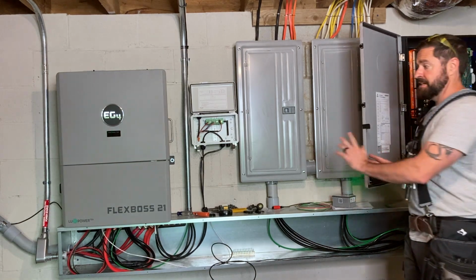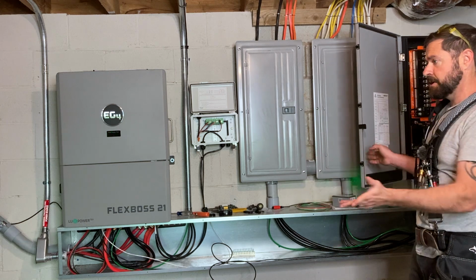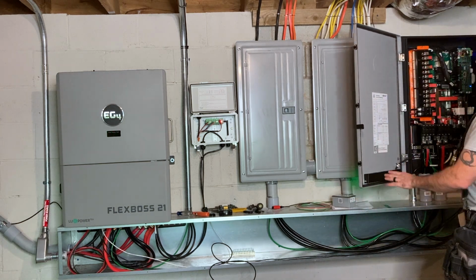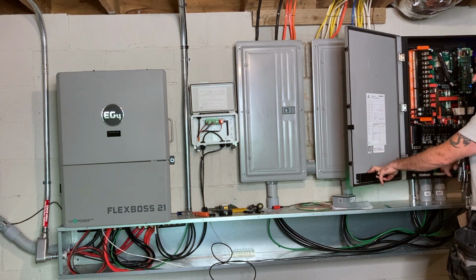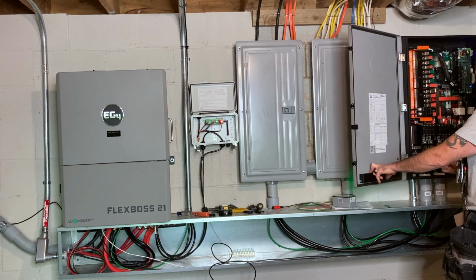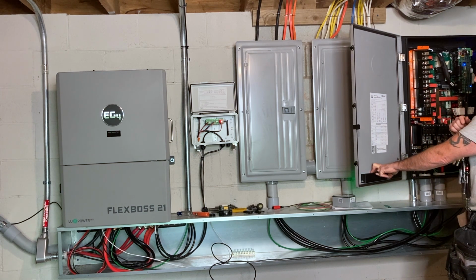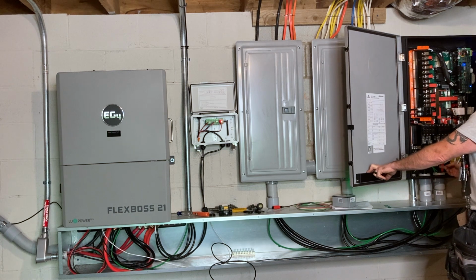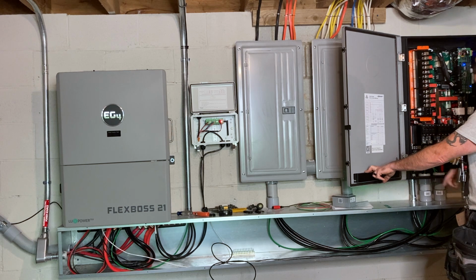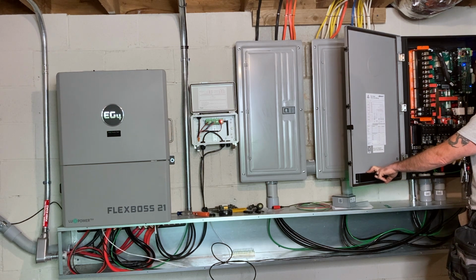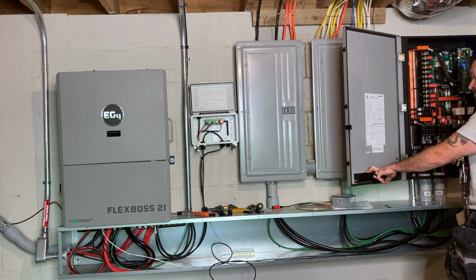Alright, since I'm going to be working with the DC bus bars, we're going to shut everything down. I'm going to turn off the FlexBoss breaker, turn off the batteries, and turn off the battery breaker in the inverter. I'm going to turn off this backed up loads disconnect and turn on the grid bypass, which I believe will allow grid power to pass through to the backed up loads panel.